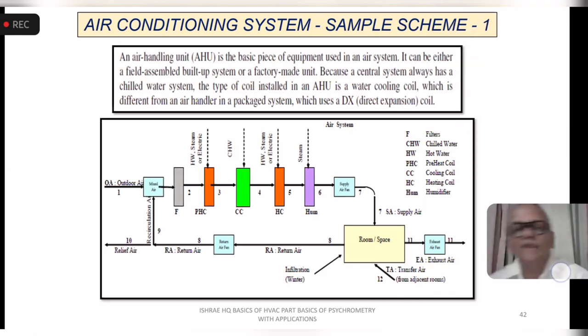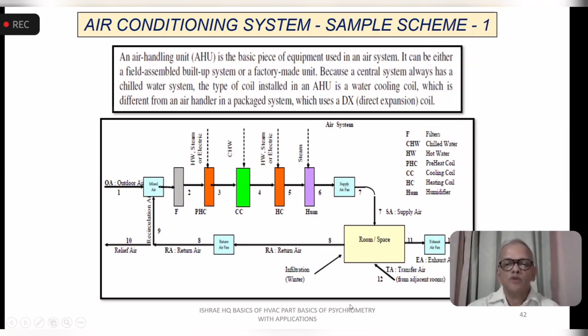Now we'll quickly look at the air handling unit system. So this is the space to be conditioned. When we are talking about the air handling unit system, you have various components: the humidifier, the heating coil, cooling coil, preheat coil, filters, and a recirculation. So you have the recirculation, outdoor air, discharge air, extract air. That is a small sketch or scheme where we are talking about the room. You have the infiltration air, and transfer air coming from adjoining spaces. So the air handling unit is the basic piece of equipment used in an air system.